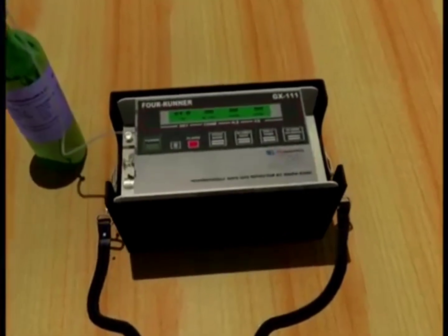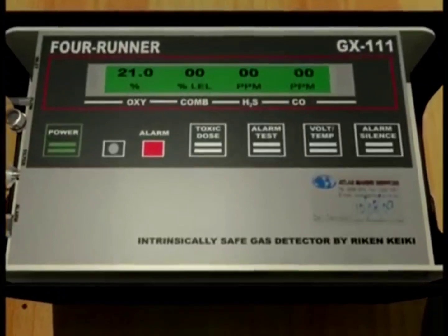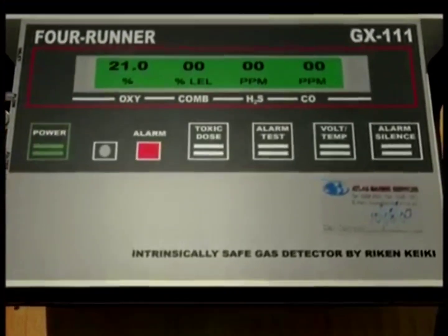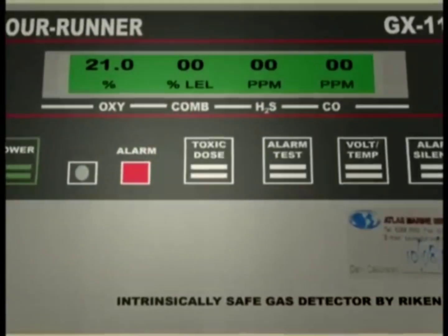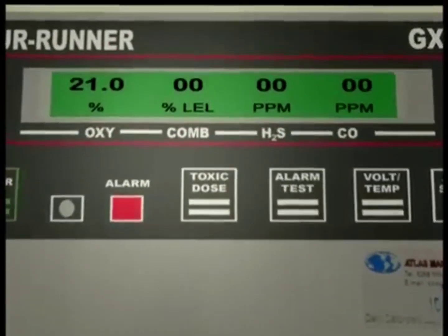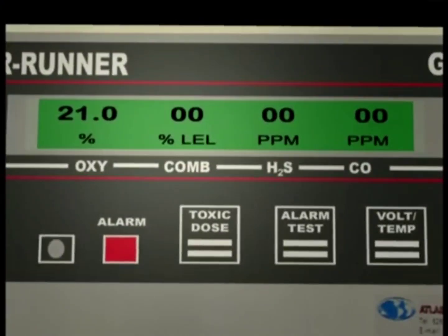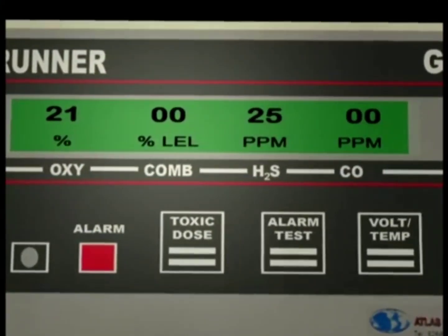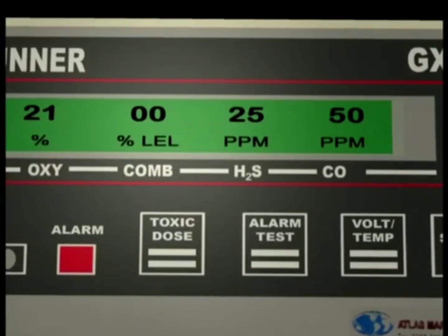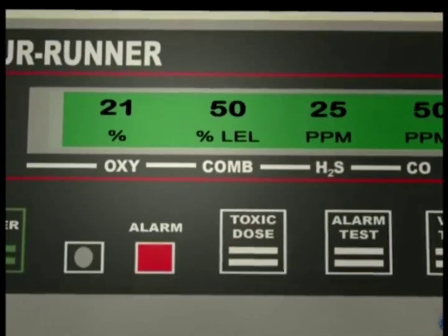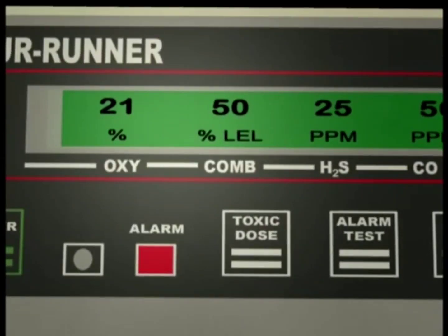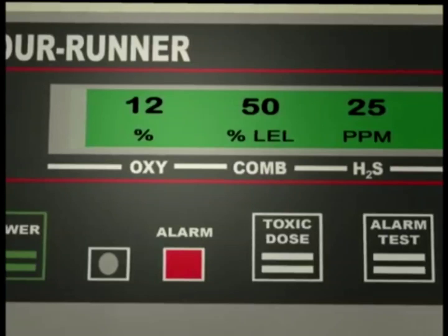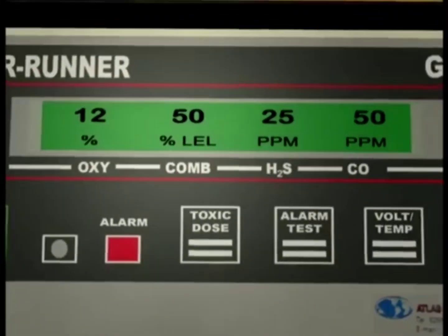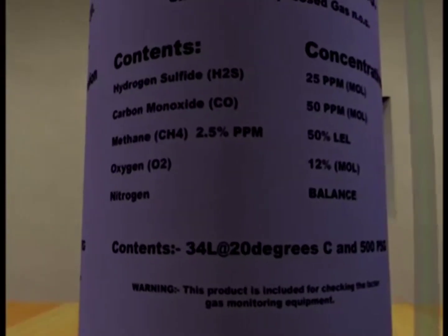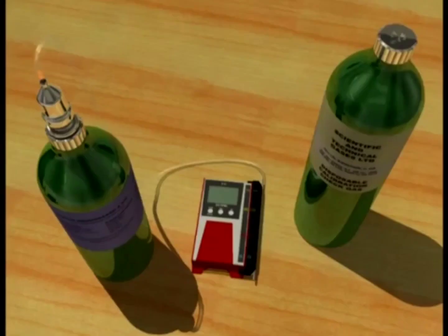A four-way detector is used for detecting four gases, namely combustible gas, oxygen, hydrogen sulfide, and carbon monoxide. The standard gas mixture used for calibrating this unit would contain hydrogen sulfide 25 ppm, carbon monoxide 50 ppm, methane 2.5%, 50% LEL, oxygen 12%, balance nitrogen. The exact concentration of gas would be marked on the label of the bottle. The personal meter also uses the 4-gas mixture for calibration.